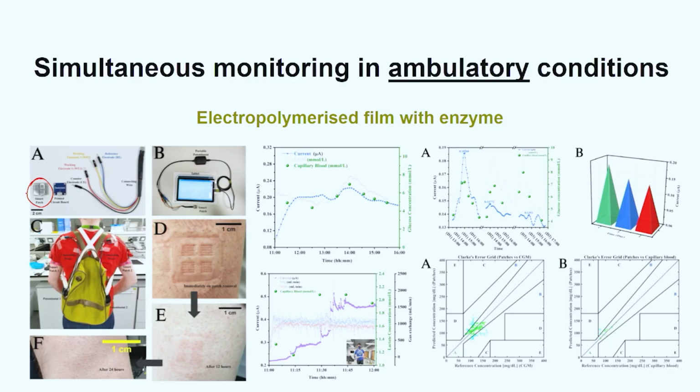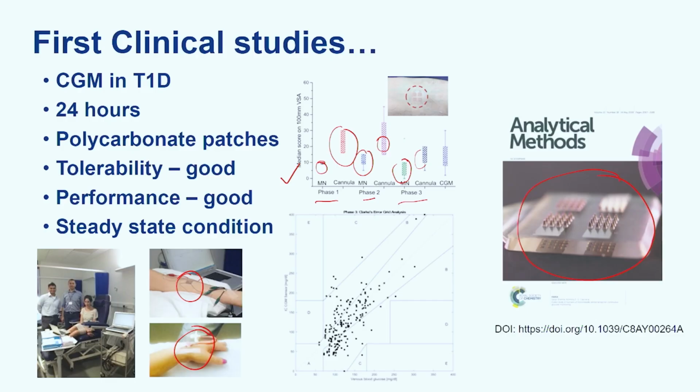This is basically the device. It looks like a polycarbonate device which looks a bit silvery in color. It's got 4 islands. The working electrodes are made up of platinum. The counter electrodes are made up of platinum as well, and you have a reference electrode which is silver, which we modify into silver chloride using a solution of ferric chloride, or we also use bleach to convert the silver into silver chloride. This is basically a PCB, because when we did the first experiments, I think I hated it, because I was the person who used to stay overnight for the 24-hour studies. And can you imagine these devices looking like spiders with wires coming out, and then the wires connected with a crocodile clip?